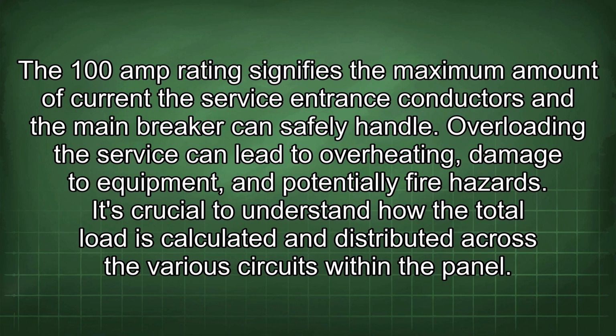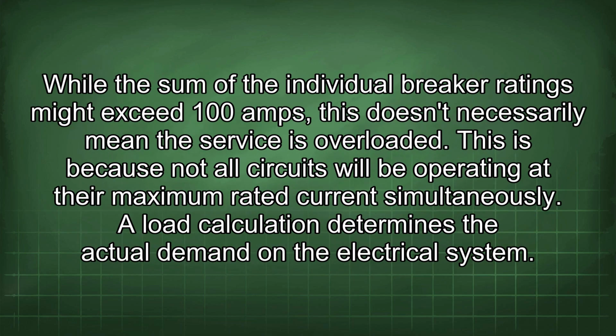It's crucial to understand how the total load is calculated and distributed across the various circuits within the panel. While the sum of the individual breaker ratings might exceed 100 amps, this doesn't necessarily mean the service is overloaded. This is because not all circuits will be operating at their maximum rated current simultaneously. A load calculation determines the actual demand on the electrical system.